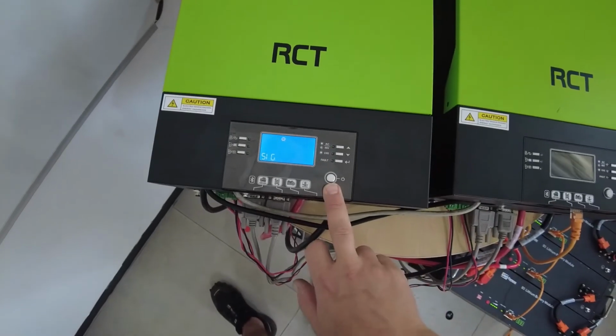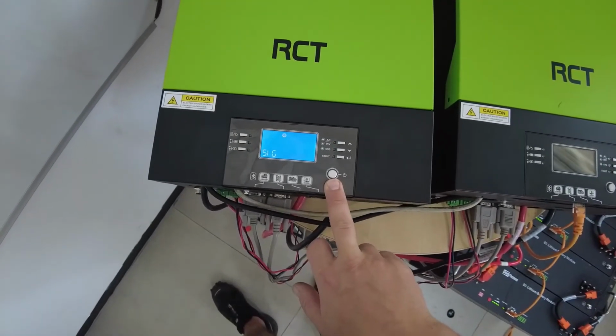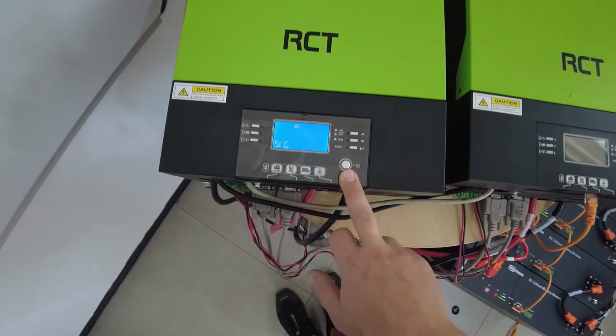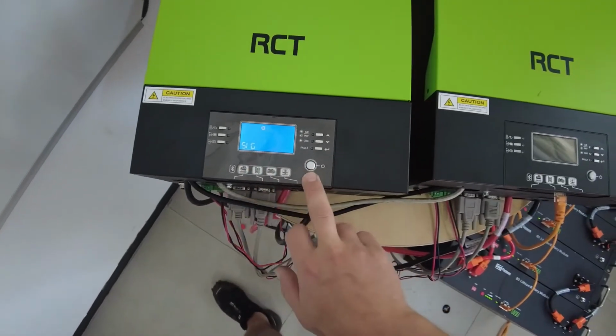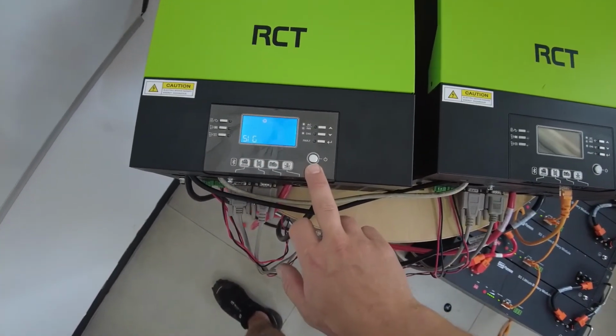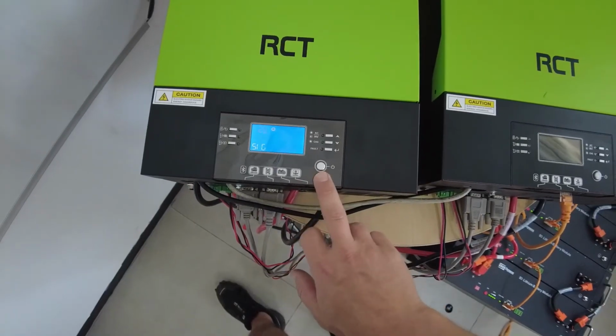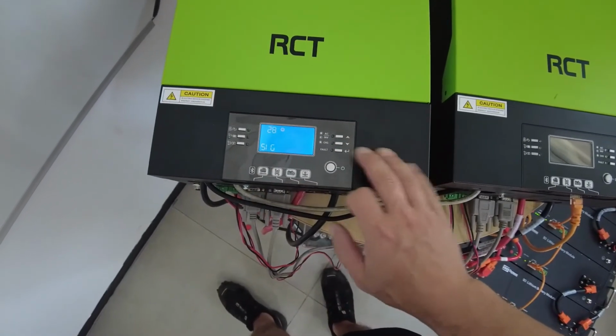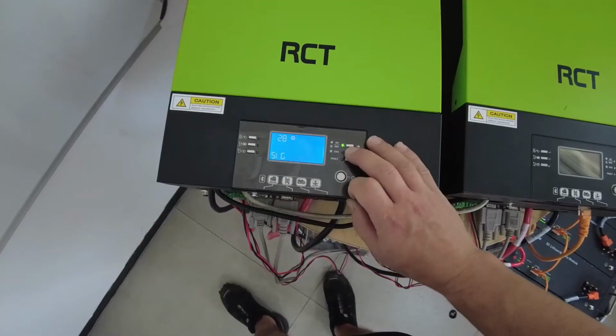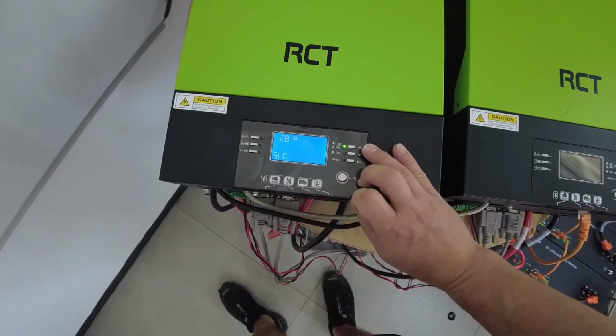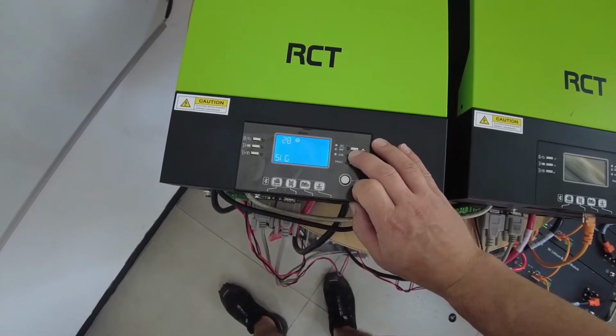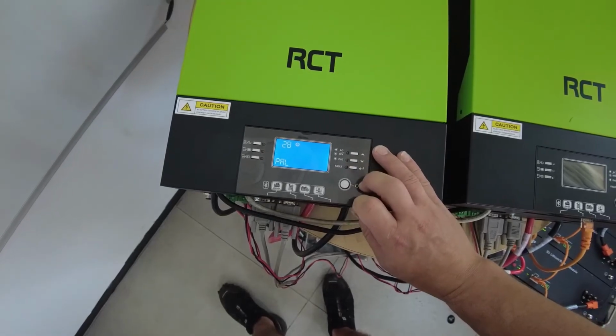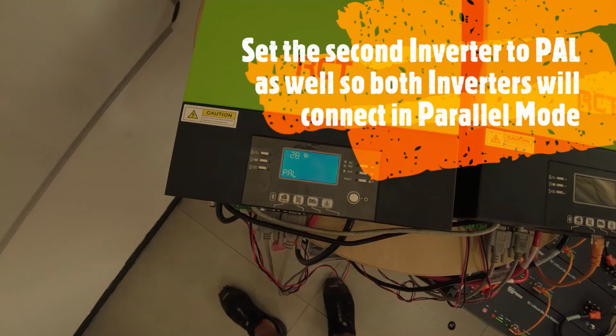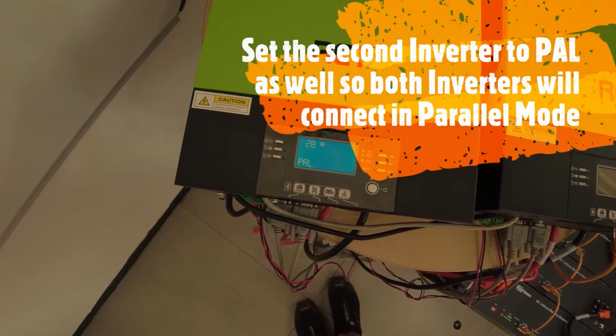So just keep in mind, if the inverter is actively on with the power button, it's engaged, it will not change. You need to shut this power button off so it's in standby before this change will take effect. So let's just change it back to PAL again. Power off the inverter, enter, you can switch it on again. Okay, you can switch this inverter off.